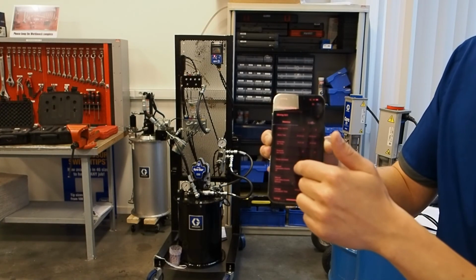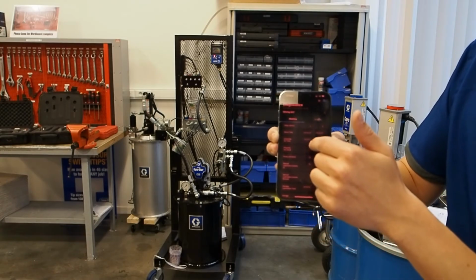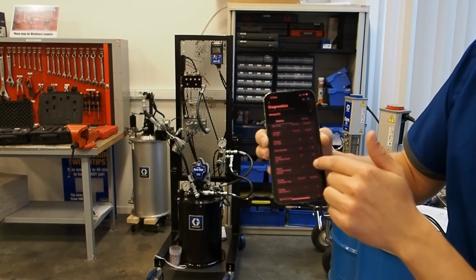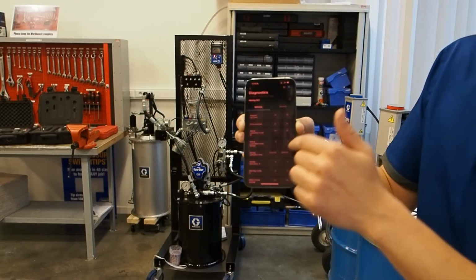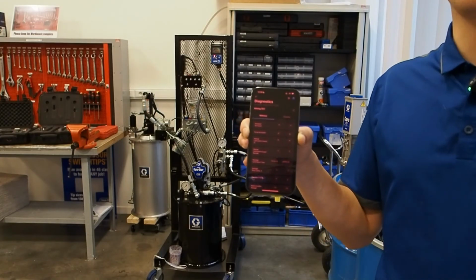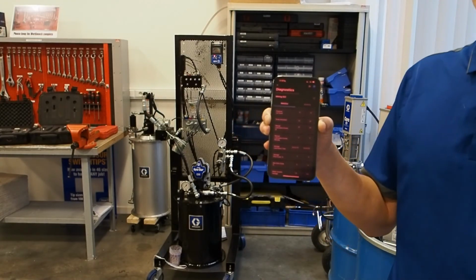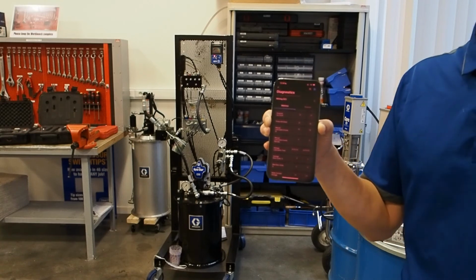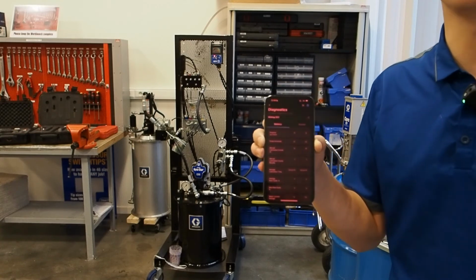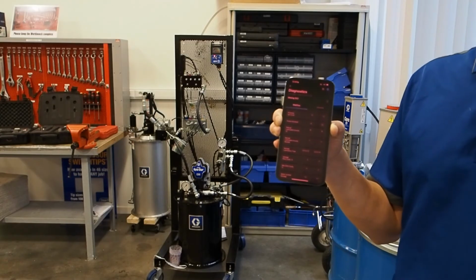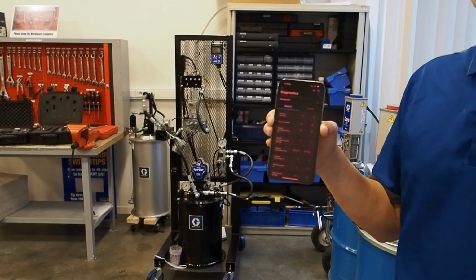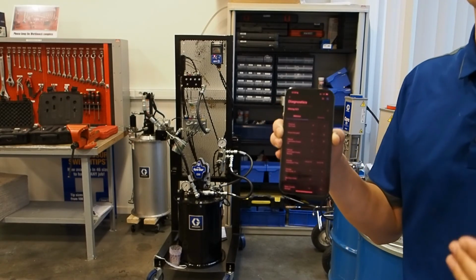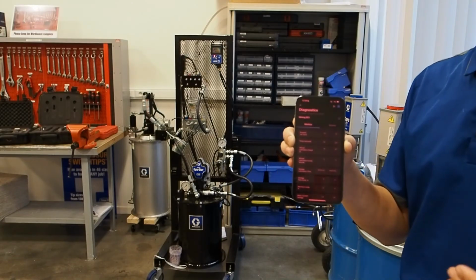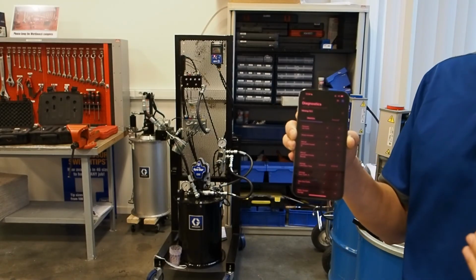Then I can also see a very interesting feature here, which is the average lubrication time. It tells me that, on average, it takes 18 seconds to build up pressure. It's very good for troubleshooting in the field to know how much time it actually takes to lubricate this piece of machinery, if it's 1 minute or 2 minutes, because it also, in a sense, shows the pumpability of a grease. Because the shorter the period of time, the faster the pump builds up pressure, meaning the grease is flowing better.